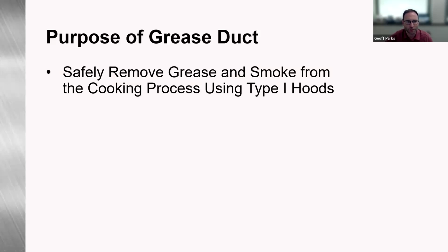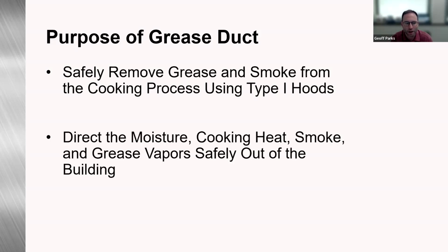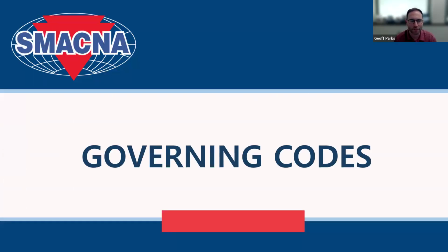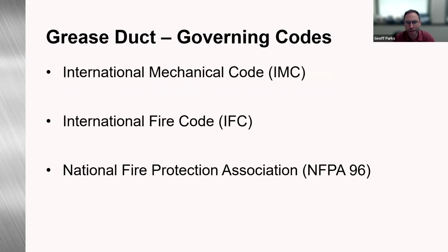So, what is the purpose of grease duct? Well, it's to safely remove grease and smoke from the cooking process using type 1 hoods, and to direct the moisture, cooking heat, smoke, and grease vapors safely out of the building. Some of the governing codes: the International Mechanical Code, the IMC, the International Fire Code, IFC, and the National Fire Protection Association, NFPA 96. These are going to be your governing codes. They provide the minimum construction requirements, for listed and unlisted, any installation requirements, minimum slopes, minimum clearances to combustibles. All that good stuff is incorporated in these codes and standards.